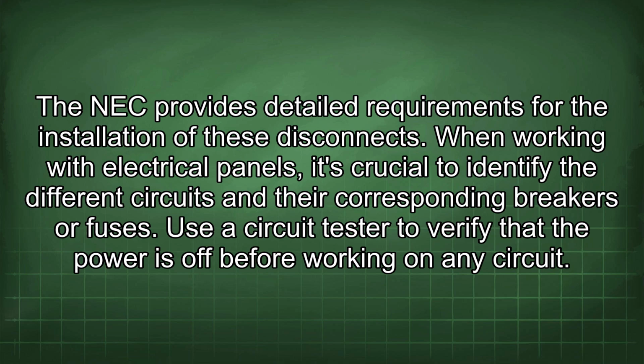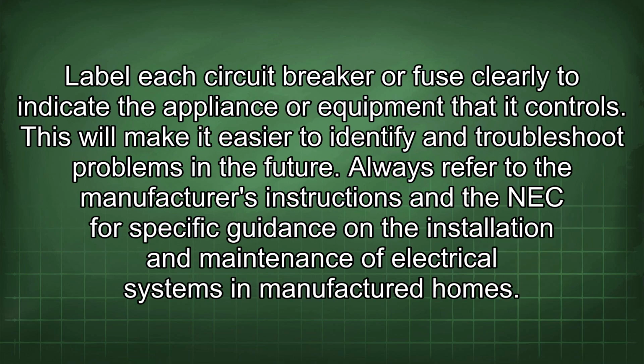The NEC provides detailed requirements for the installation of these disconnects. When working with electrical panels, it's crucial to identify the different circuits and their corresponding breakers or fuses. Use a circuit tester to verify that the power is off before working on any circuit. Label each circuit breaker or fuse clearly to indicate the appliance or equipment that it controls. This will make it easier to identify and troubleshoot problems in the future.